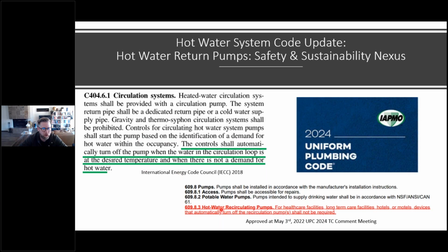And so there's a new allowance in the Uniform Plumbing Code that says for healthcare facilities, long-term care facilities, hotels or motels, devices that automatically turn off their circulation pump or pumps shall not be required. So this is at least for UPC adopting jurisdictions, which is about half the country, a little less than half. This is an opportunity to have something to point to and say, hey, we don't want to turn off the aquastat, or we don't want to turn off the recirculation pump because of the health and safety concern.